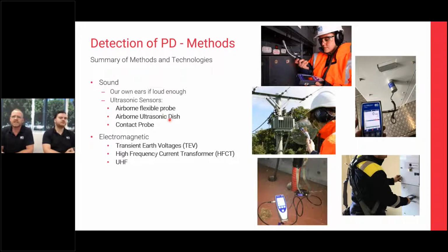Okay, they listen in the 40 kilohertz range where human beings can't hear. And then we've got electromagnetics. So whenever a spark occurs, a little spark will jump a gap. A ball of energy, in a range of electromagnetic frequencies, will be given off, and that signal will propagate away from its source in all directions.